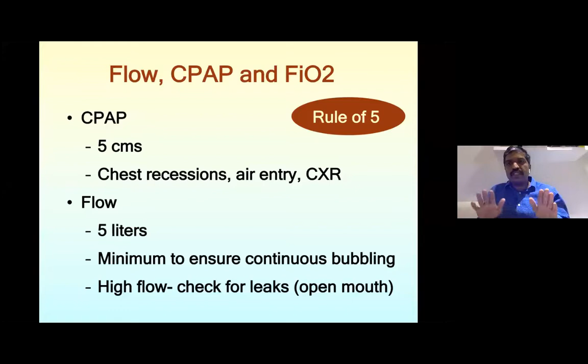There are no leaks in the circuit, but still there is no bubbling. So what should you do? If there is no bubbling, first you have to go back and see if there are any leaks in the circuit. If there are no leaks in the circuit, increase the flow to 6 liters. Still, if bubbles are not there, increase the flow to 7 liters.